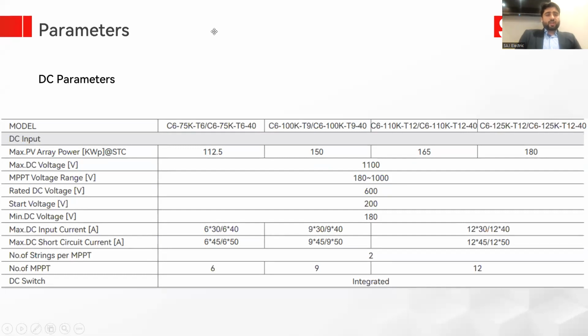When we talk about the DC parameters of the C6 inverters, they start from 75 kilowatt to 125 kilowatt. The 75 kilowatt inverter has 6 MPPTs. Every MPPT has a 40 ampere rating. The maximum DC input current and the short circuit current rating is 50 ampere. The 100 kilowatt has 9 MPPTs, the 110 kilowatt has 12 MPPTs, and the 125 kilowatt has 12 MPPTs and 24 inputs. Every MPPT has two string inputs. A DC switch is integrated.